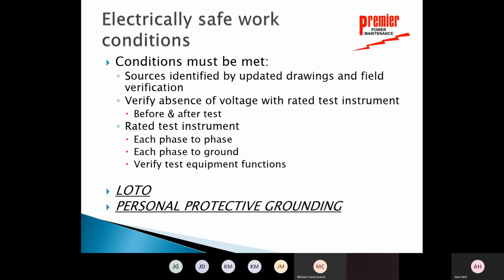So, what's it take to create this electrical safe work condition? There are certain conditions that have to be met. First of all, the sources identified of the equipment you're working on. So you're working on a specific piece of equipment. Those sources have to be identified on updated drawings and field verifications. So it's unlike most places we work at: you're going to have drawings, and not only do you have drawings, but you're going to verify the drawings are correct by field verification.